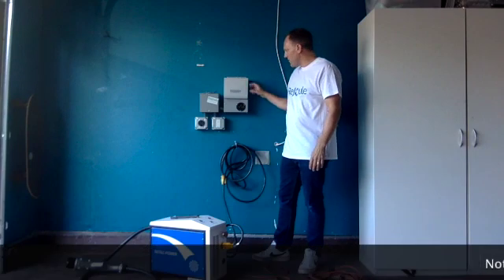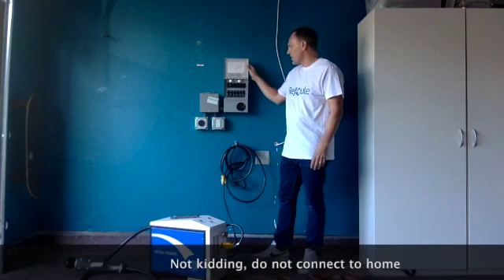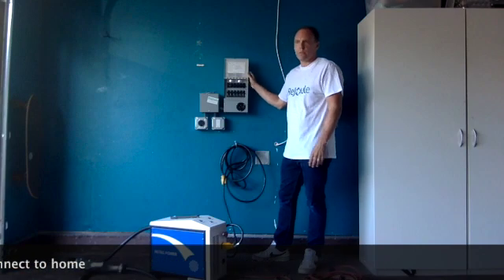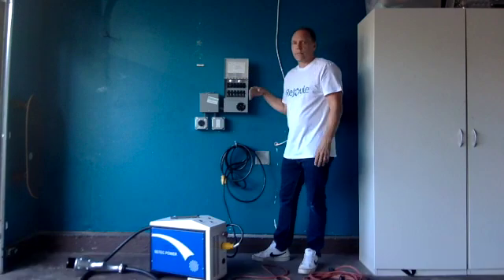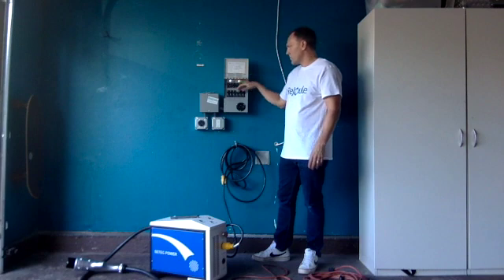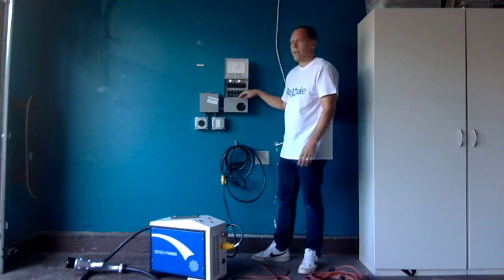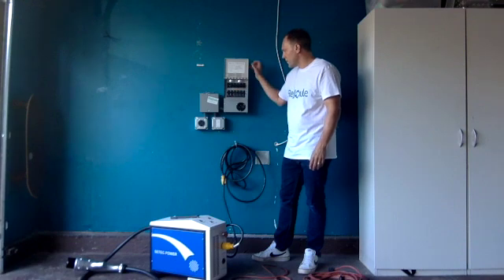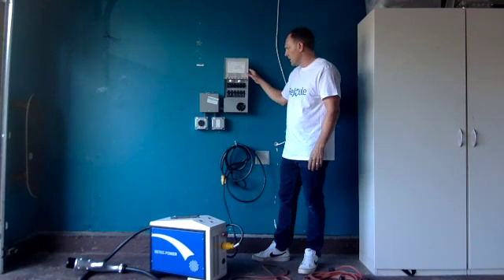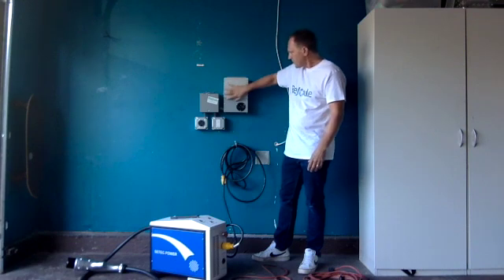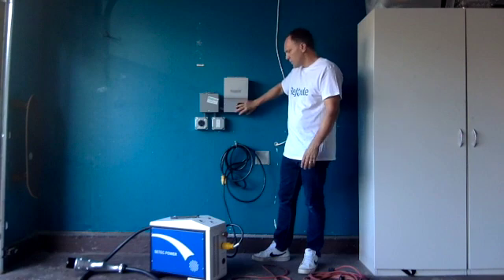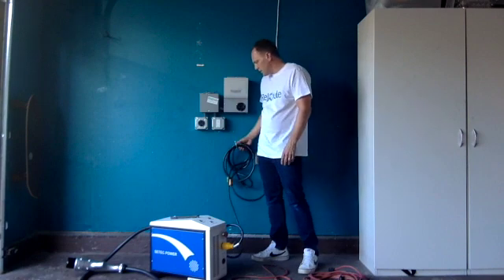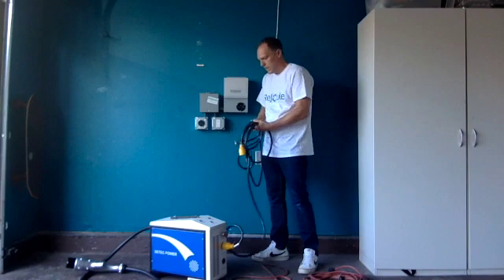But I have installed a transfer switch here. This manual transfer switch can disconnect from the home, shuts everything off from the grid, and then has a critical load panel that's been wired to some critical loads in the house, like the fridge. This can go up to 30 amps, so it's pretty small, but it can get a decent amount of loads on the house.